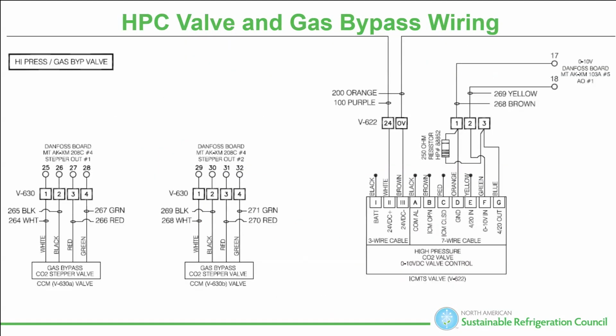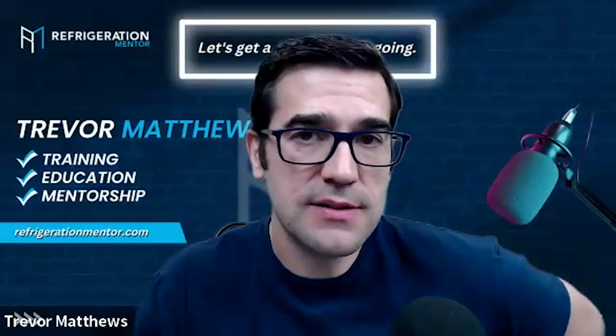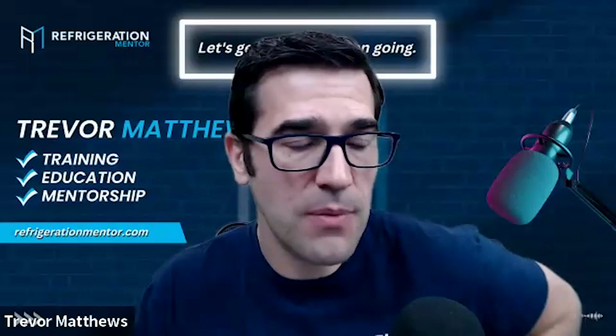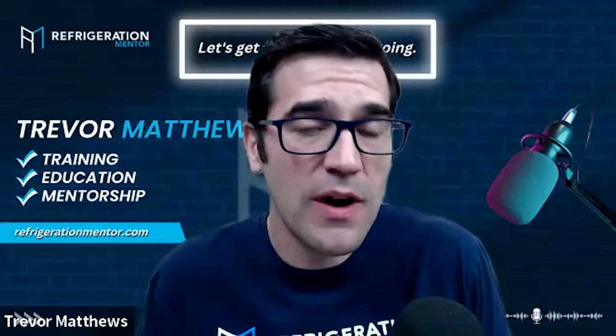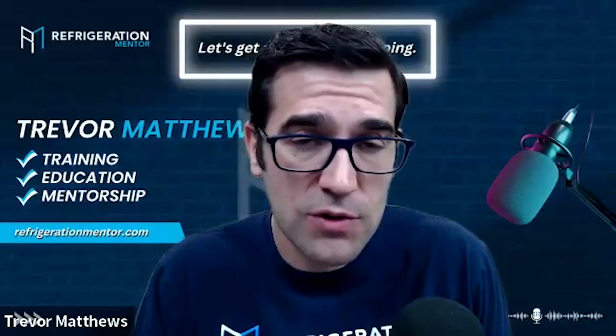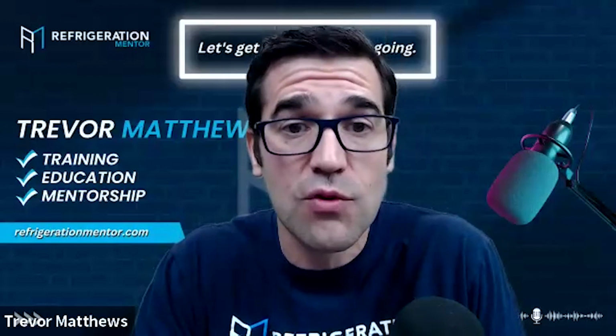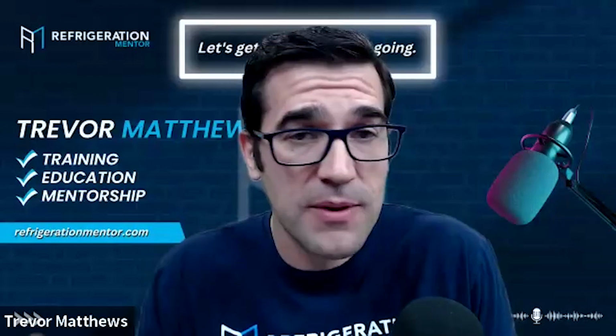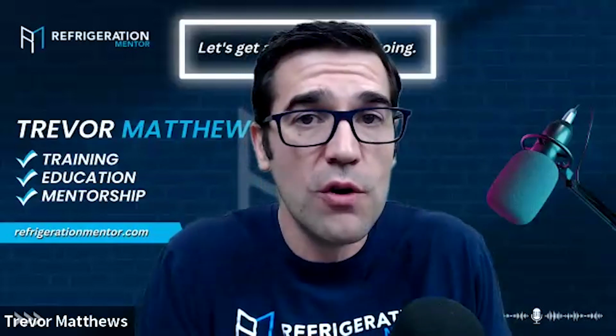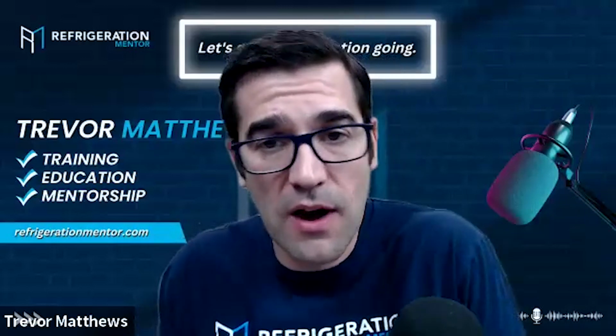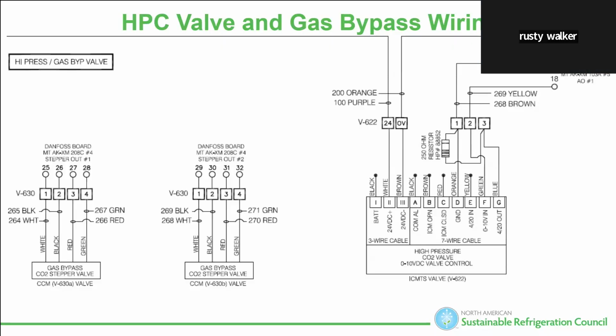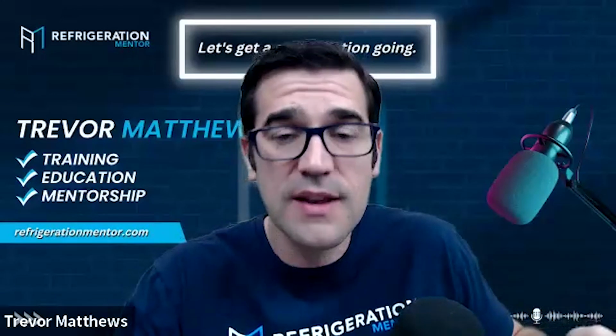The thing I want to point out is that we as technicians are always putting out fires, and things aren't working all the time. When a system is running normally, this is why everyone should do a couple of startups. When the system's running normally, that's when you should take your meter out and go along the wiring diagram so you know what it should look like when running normally, versus when you go there and you've never been at the system before, or the only time you've been there is when it has an electrical issue. If you don't know what it's supposed to look like normally, it's going to be harder to troubleshoot that system. So start troubleshooting systems that are running fine already and start using your meter, just like Rusty's talking about, going across and getting an understanding.